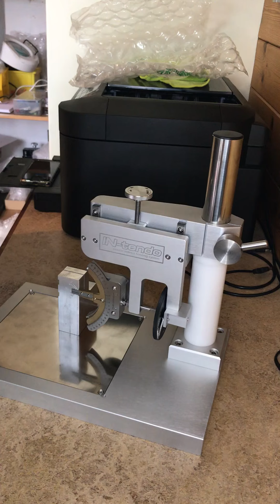Right, I've showed you the assembly. Now I'm going to show you if you need to check the calibration. This is only if some things come loose somewhere on the mechanism, between the mechanism body. The only things that could come loose are these screws here, which hold the back of the linear slide, maybe the linear slide to the body. They shouldn't be loose, but just in case. Over time they could be, or if somebody has decided to play with it to see how it's made.